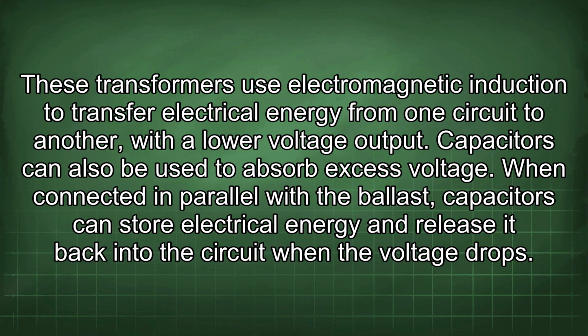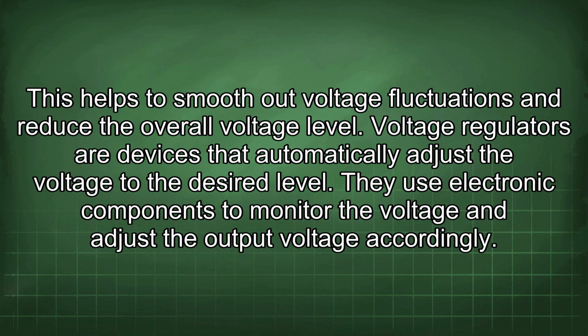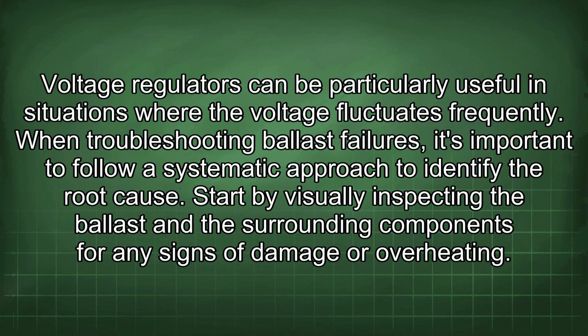When connected in parallel with the ballast, capacitors can store electrical energy and release it back into the circuit when the voltage drops. This helps to smooth out voltage fluctuations and reduce the overall voltage level. Voltage regulators are devices that automatically adjust the voltage to the desired level. They use electronic components to monitor the voltage and adjust the output voltage accordingly. Voltage regulators can be particularly useful in situations where the voltage fluctuates frequently. When troubleshooting ballast failures, it's important to follow a systematic approach to identify the root cause.